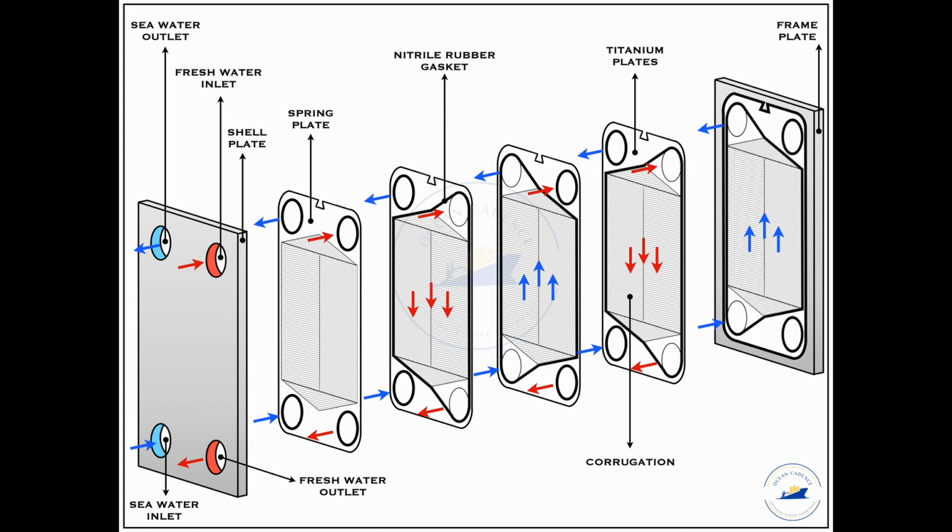The plates that are being shown here are mostly of titanium grade because the tolerance limit of the plate for lateral expansion as well as the compressive forces as well as its distortion due to heat exchange should be minimal and the other tolerances should be maximum. So titanium plates are being used, and because these plates have a very long service life which is as good as the lifespan of the vessel, the cost ratio is not very much bothersome.